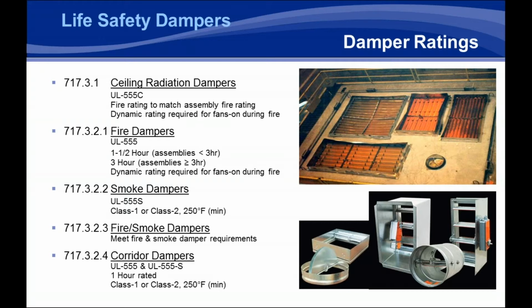tested. In order to do that under dynamic flow, it would be very difficult to achieve the ratings in the damper. It would require significant additional cost to the damper and the overall assembly to pass that test, as these are load-bearing structures, and that will need to go through this fire rating and are combustible. So as they're deteriorating, they need to have the load of the fan, or UL feels they need to have the load of the fan and the damper at the same time. Unfortunately, there's no good way to mimic that. There's no good place to put the furnace without weakening the structure of that test floor ceiling assembly and limiting your ability to withstand that load for up to an hour. Because of that, there's no dynamic rated ceiling radiation damper currently on the market.